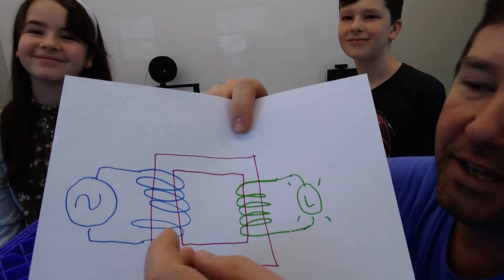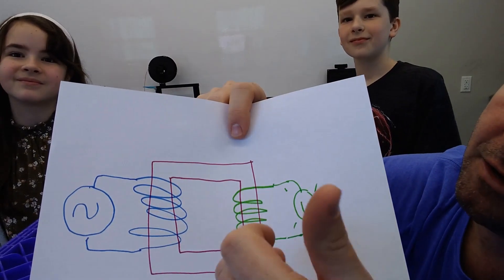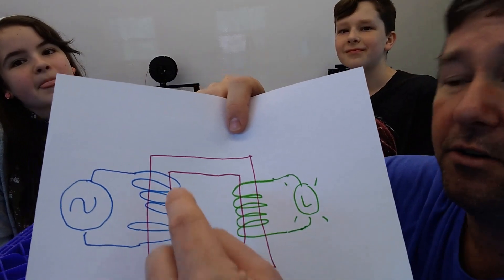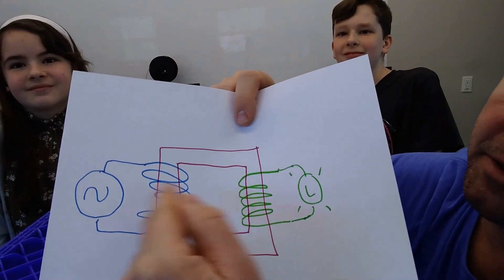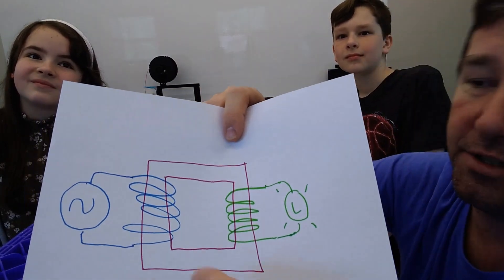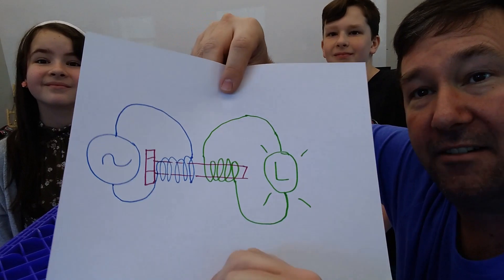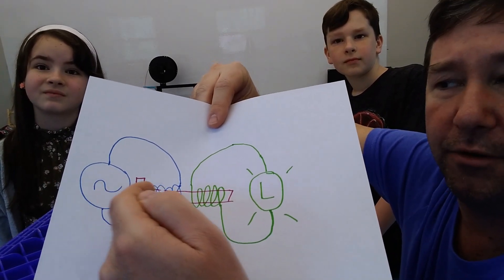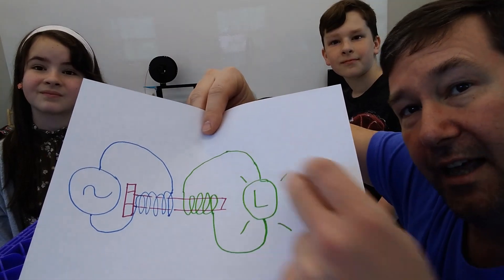This is a typical transformer that you would see. You would have AC power on this side going to a winding of wire, and then you would have this iron block going all the way around it. There would be a secondary winding of wire that would go to another voltage. Usually you would have 480 here, and if there are four times fewer turns on the secondary side, that would bring it down from 480 to 120 — it depends on the number of turns. This iron block transfers the magnetic flux created on the AC side over to the secondary side. Our setup uses a bolt through a contactor coil with another contactor coil on top, and the bolt extends that magnetic flux over to the second coil — that's why the light is lighting up.